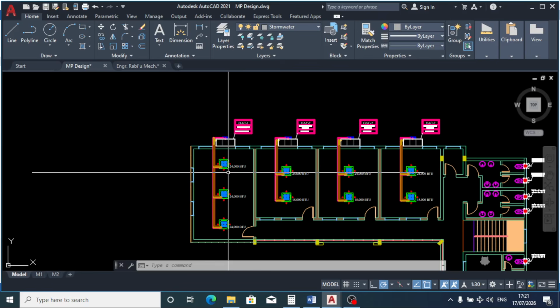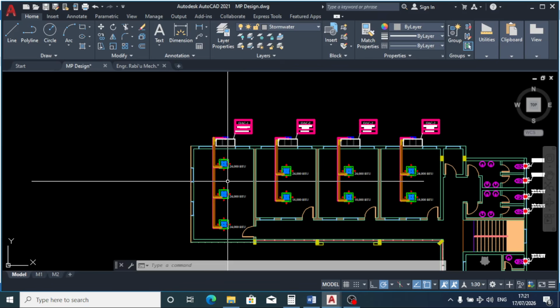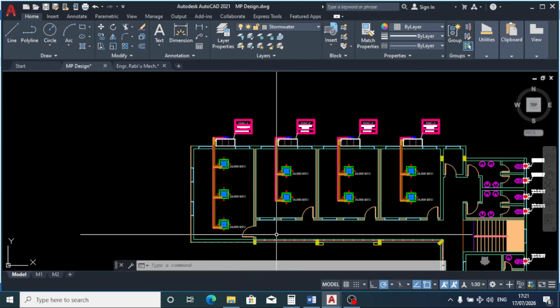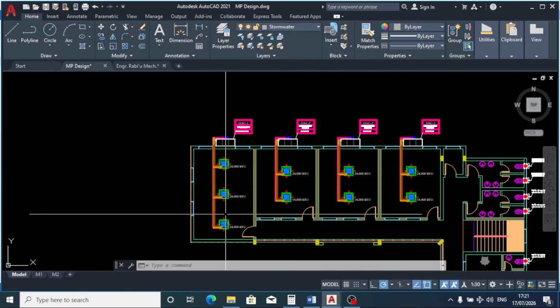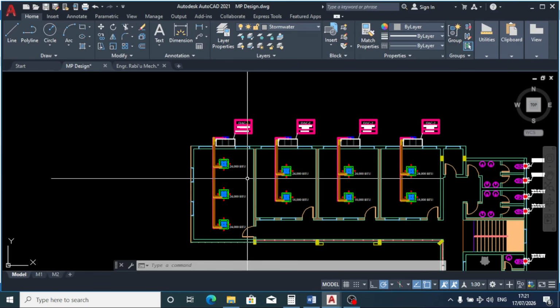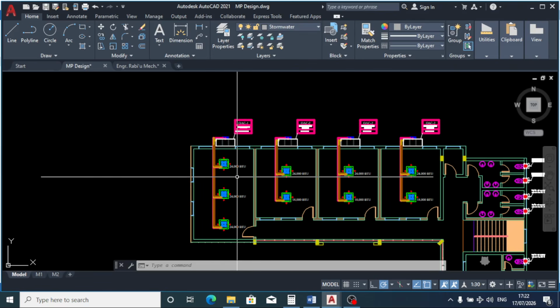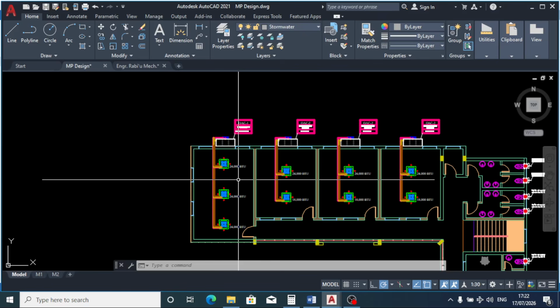Remember, our architect didn't furnish us with the schedule of the components, like the doors, the walls, the types of glass for the windows, and also we assume that for this conference room there is going to be use of electric kettles and fridge, which all this contributed to high cooling load capacity.